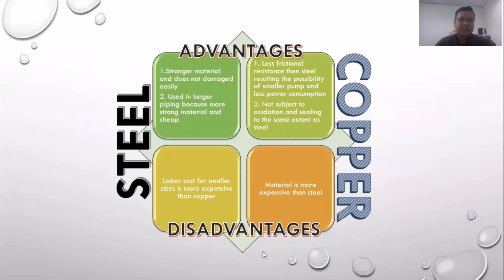So what are the advantages and disadvantages of both materials? Steel is a stronger material and doesn't get damaged easily, and it uses a larger pipe size because it is a stronger material, and it is cheap. But copper has less frictional resistance, resulting in the possibility of a smaller pump and less power consumption because of lower resistance. And it is not subject to oxidation and scaling to the same extent as steel. So as we know, copper is resistant to corrosion. As for the disadvantages, for steel, the labor cost of smaller size is more expensive than copper. But for copper, the disadvantage is that the material is more expensive than steel.